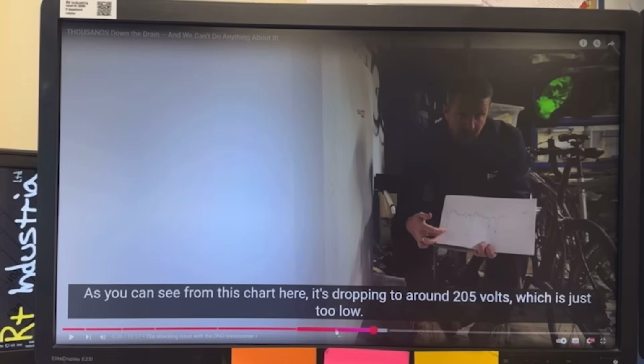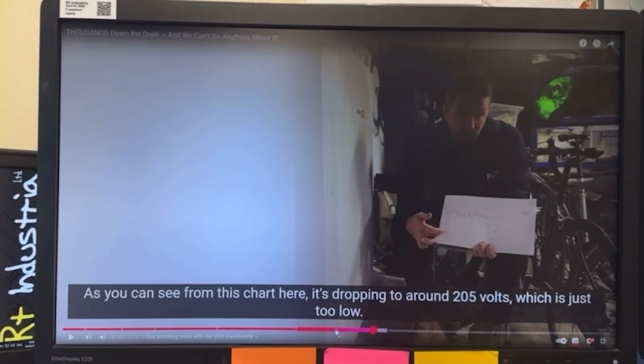And now you're in trouble at the other end of the scale because voltage optimizers don't vary to adjust the voltage. In a PID loop, you keep a voltage in range: it goes up, you push it down; it goes down, you push it up. So if it were optimizing properly, it'd do that and keep it level. This just goes from here to here. So, yeah, tough luck with the voltage optimizer.